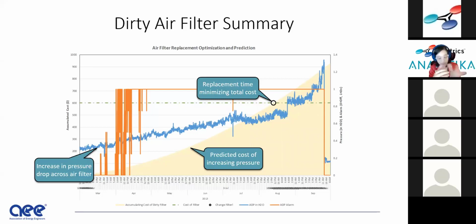So in a preventative maintenance program or a reactive maintenance program, you might see this alarm come on, this differential pressure alarm come on, and say, oh my gosh, I need to replace my filter. You'll see it's sporadic in the beginning because their differential pressure is kind of jumping above some sort of set point that alarm is set for and then dropping below. So your alarm is kind of flagging on and off. I'll mention that persistent alarms or alarms that do that are oftentimes ignored because they're not trusted, and other alarm points might not be working right, and so you might assume that all are bad. So that's another problem with just relying on an alarm point, and that's a big way that analytics can help you. It actually can find sensor errors, and that's a big part of what we do.